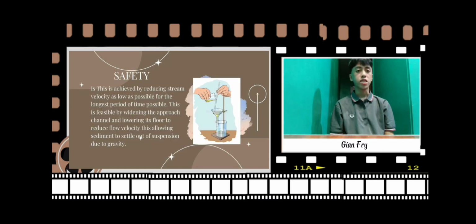The safety in using the sedimentation process. This is achieved by reducing stream velocity as low as possible for the longest period of time possible. This is feasible by widening the approach channel and lowering its floor to reduce flow velocity, allowing sediment to settle out of suspension due to gravity.